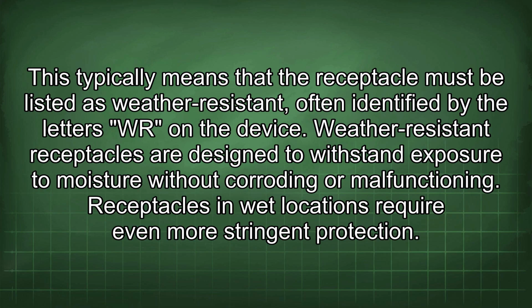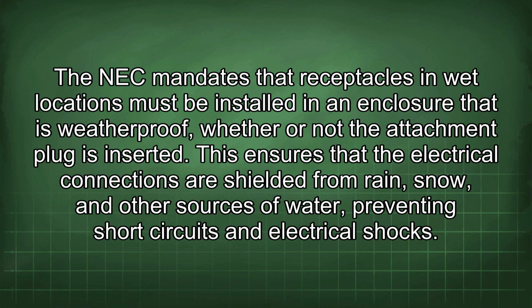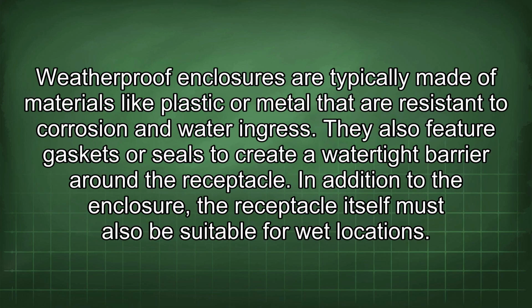Receptacles in wet locations require even more stringent protection. The NEC mandates that receptacles in wet locations must be installed in an enclosure that is weatherproof, whether or not the attachment plug is inserted. This ensures that the electrical connections are shielded from rain, snow, and other sources of water, preventing short circuits and electrical shocks. Weatherproof enclosures are typically made of materials like plastic or metal that are resistant to corrosion and water ingress. They also feature gaskets or seals to create a watertight barrier around the receptacle.